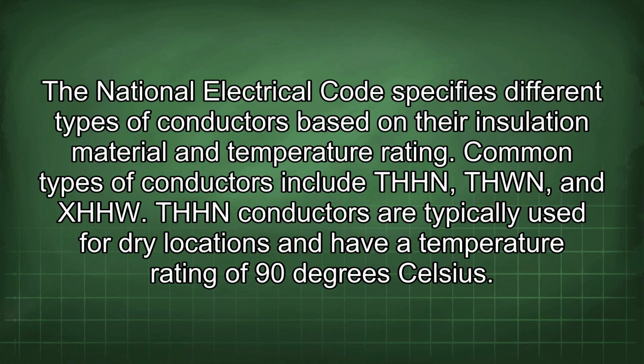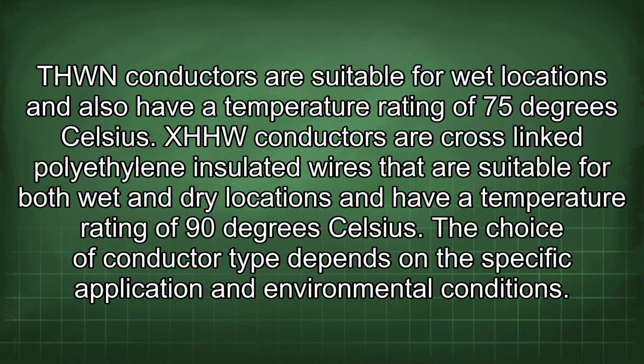The National Electrical Code specifies different types of conductors based on their insulation material and temperature rating. Common types of conductors include THHN, THWN, and XHHW. THHN conductors are typically used for dry locations and have a temperature rating of 90 degrees Celsius. THWN conductors are suitable for wet locations and also have a temperature rating of 75 degrees Celsius. XHHW conductors are cross-linked polyethylene insulated wires that are suitable for both wet and dry locations and have a temperature rating of 90 degrees Celsius.